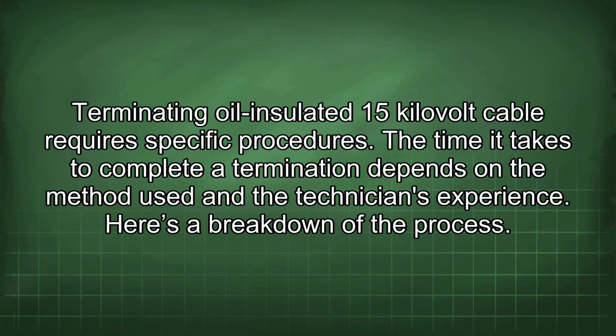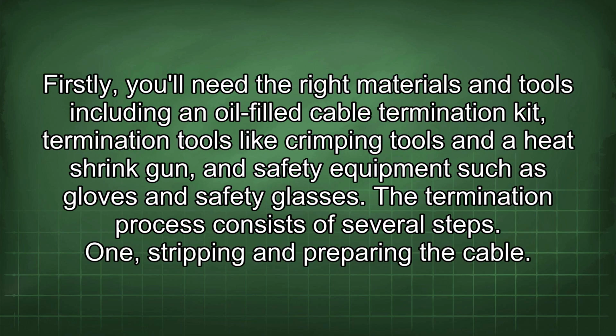Terminating oil insulated 15 kilovolt cable requires specific procedures. The time it takes to complete a termination depends on the method used and the technician's experience. Here's a breakdown of the process. Firstly, you'll need the right materials and tools, including an oil-filled cable termination kit, termination tools like crimping tools and a heat shrink gun, and safety equipment such as gloves and safety glasses.